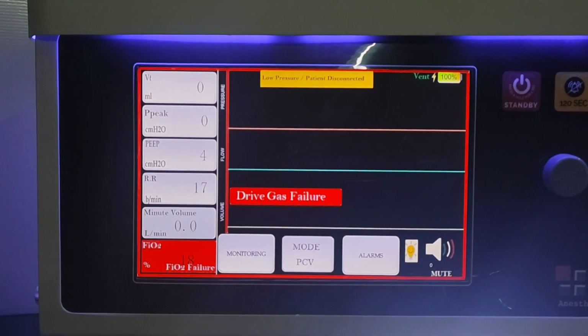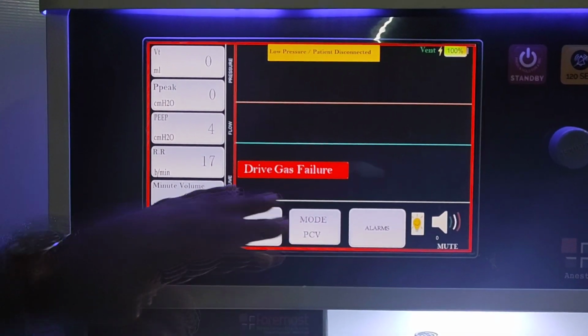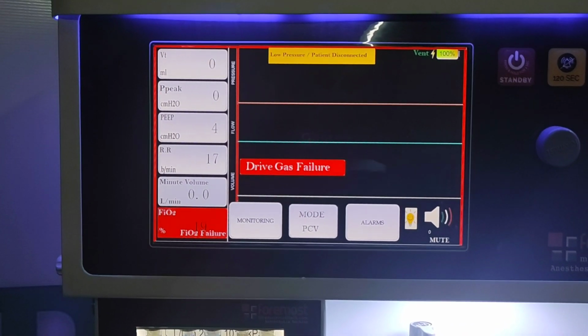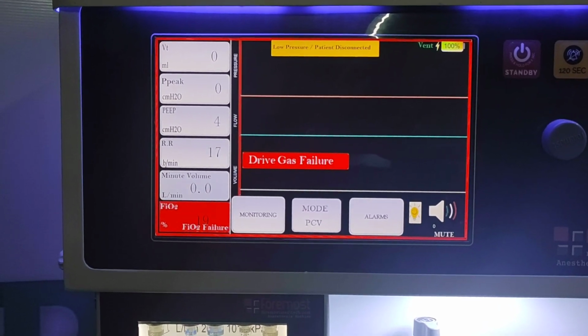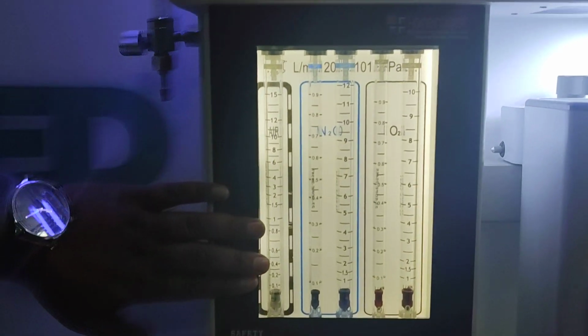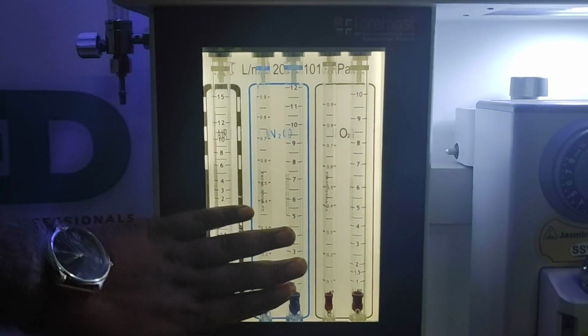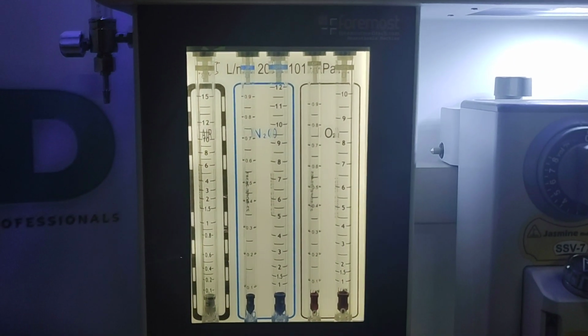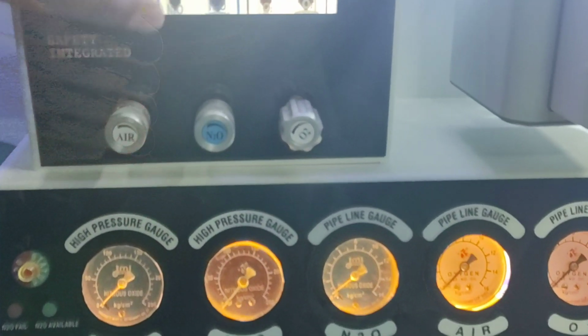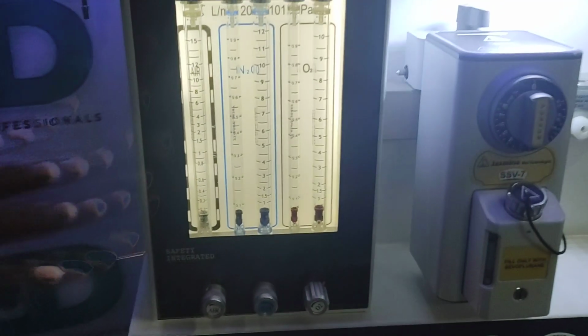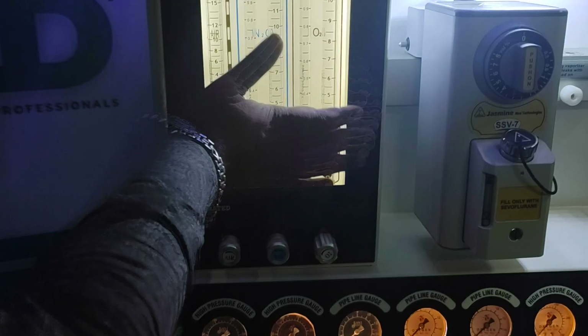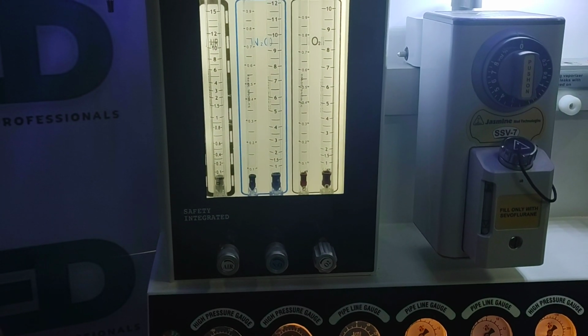So currently we have not connected any gas, so it's showing drive gas failure because we have not connected any oxygen source or any nitrous source, anything. Now coming to here, these are your flow meters. One is for air, and the other two are for N2O and O2. For high flow and low flow, both tubes are there. All the compact things are there, and it also comes with a hypoxia guard.